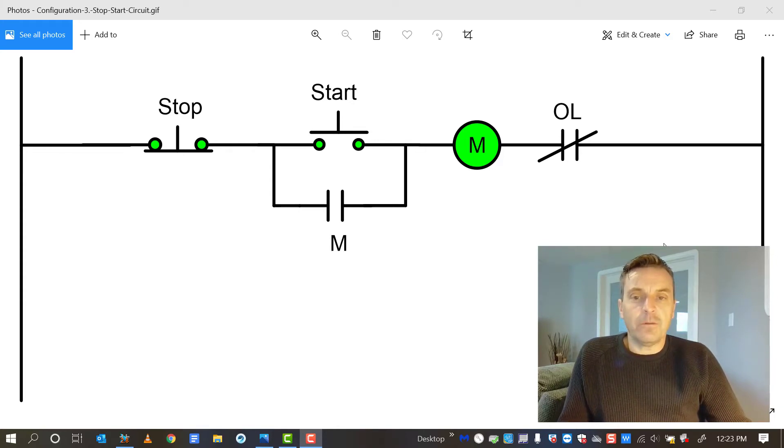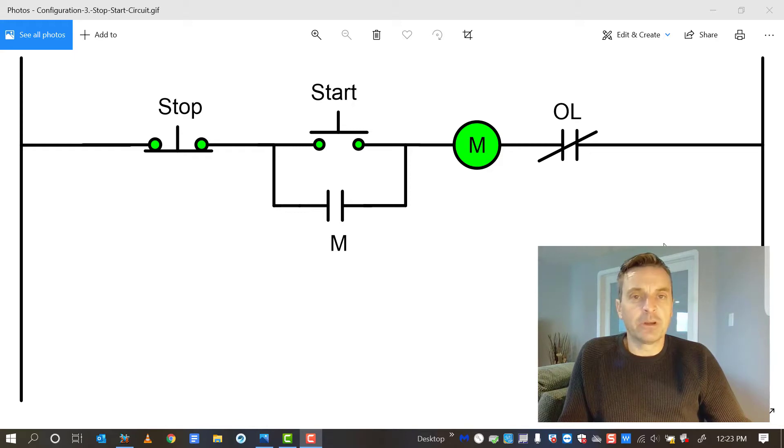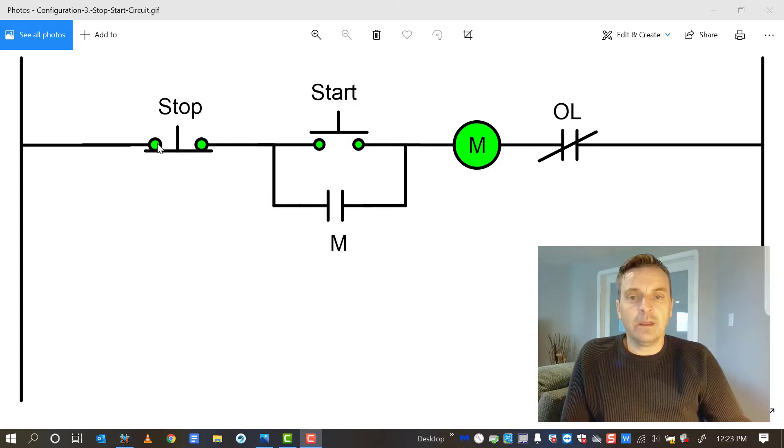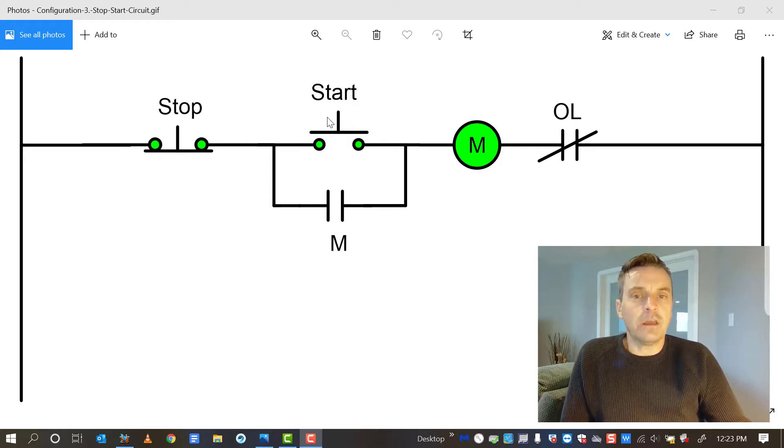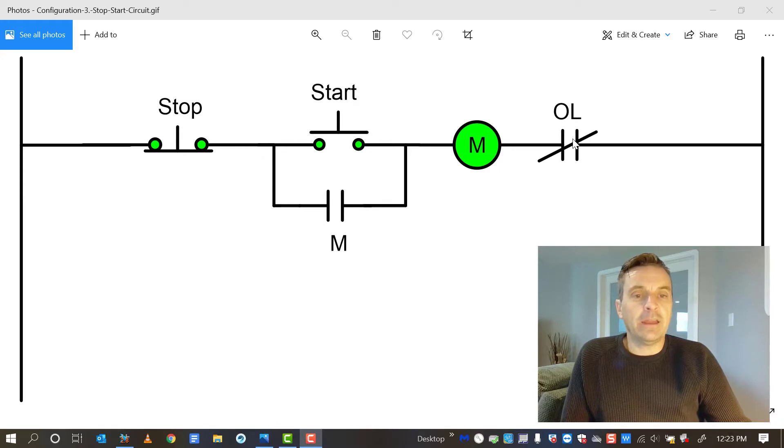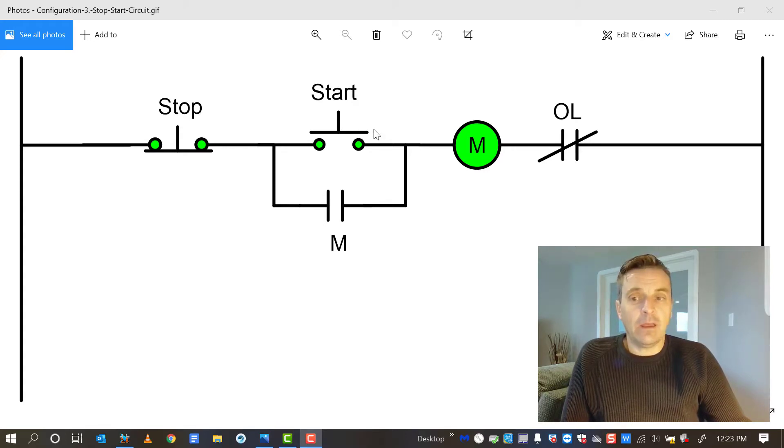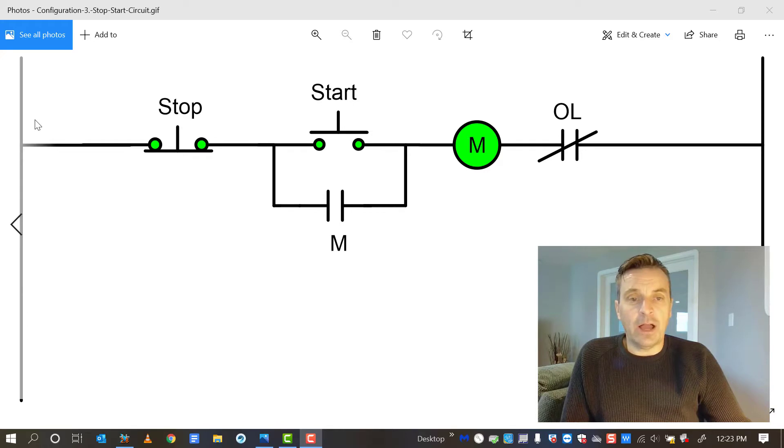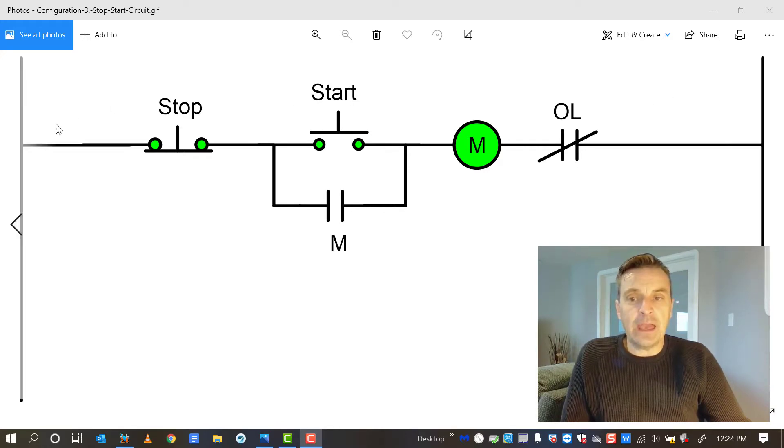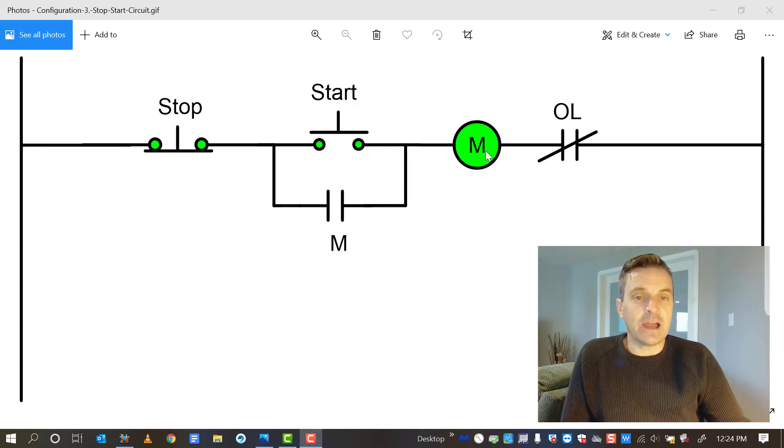So right on the screen we have a start-stop station for a motor control circuit. We've got our normally closed stop button, a normally open start, a normally open holding contact, our motor coil, and our overload contact, normally closed. This would be line one and this would be neutral or line two, and current and voltage would flow through these and energize that coil.